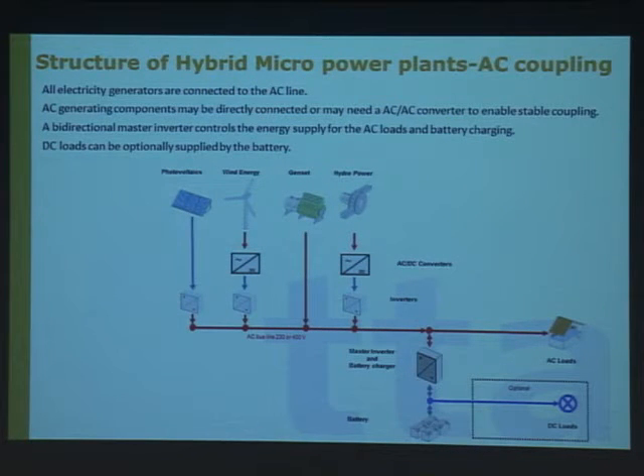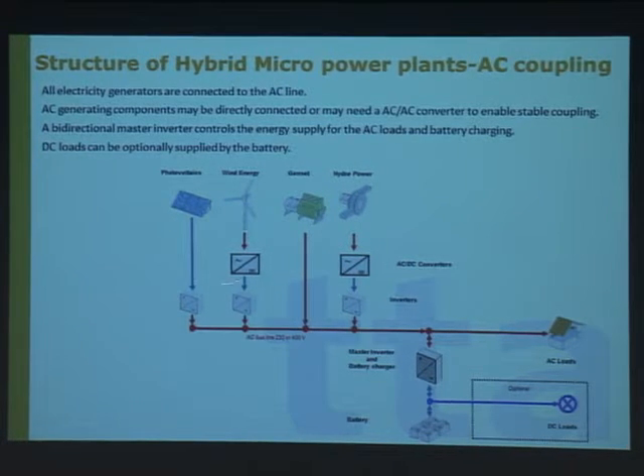From the electrical point of view, there is a lot of discussion, which I don't think is that relevant, but I'll point it out: whether we should go to what is called AC coupling. That means the different devices are interconnected through the AC feeder line. It has certain advantages and disadvantages. This is the typical diagram where you have an AC bus that also feeds the loads, to which you connect different generators through inverters, and if you need storage, you connect through a bidirectional inverter.